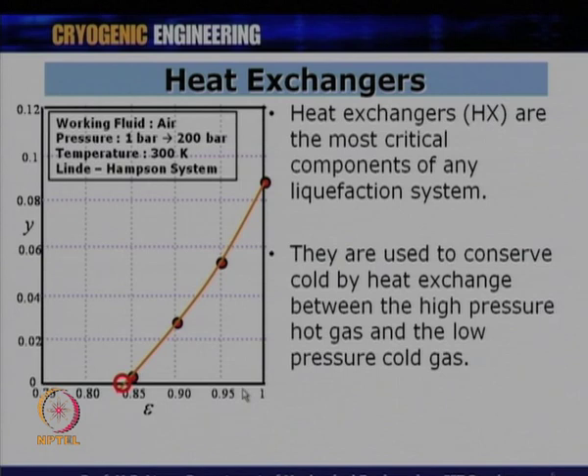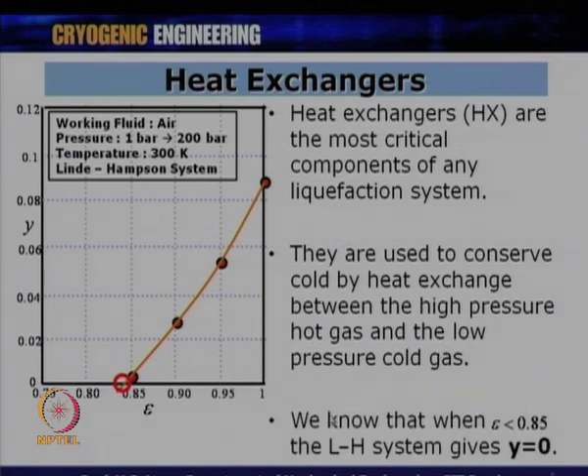One cannot always reach 97–98% effectiveness due to fabrication limitations, assembly limitations, and pressure drop in the system. All these must be considered when designing a heat exchanger, but one should strive to attain at least 95% effectiveness. The effectiveness must be more than 85% and ideally more than 90–95% to get a reasonably good yield value.